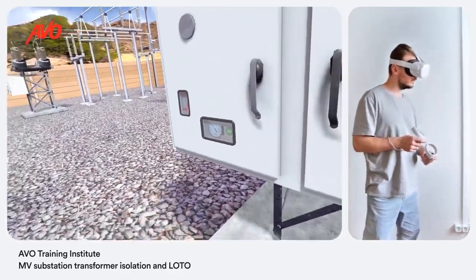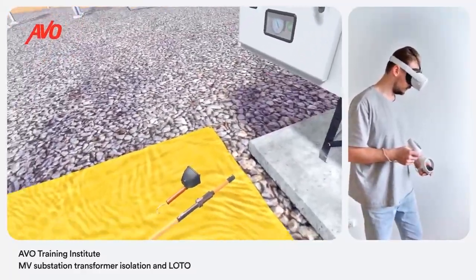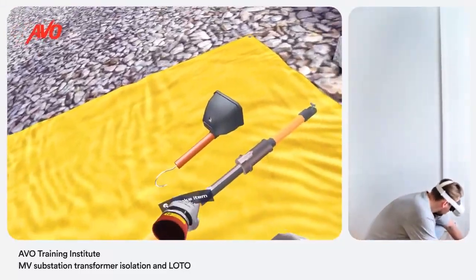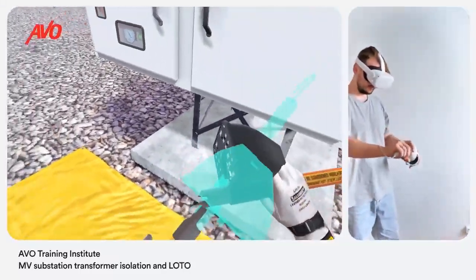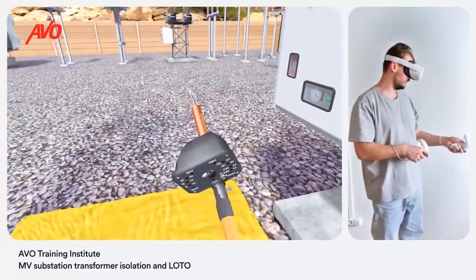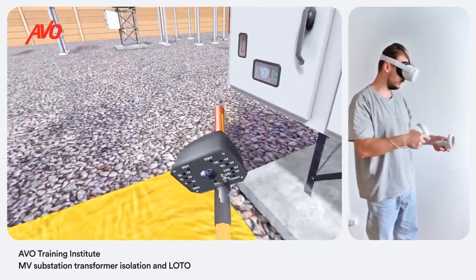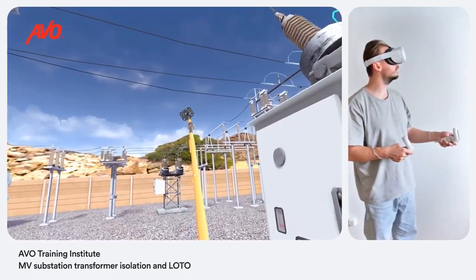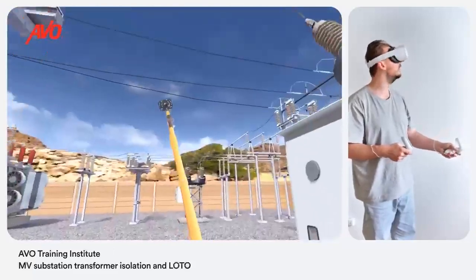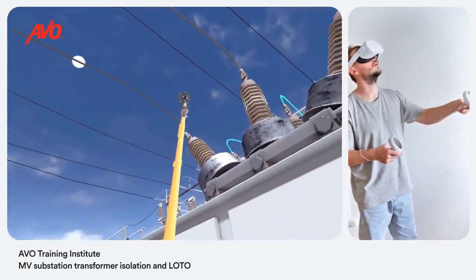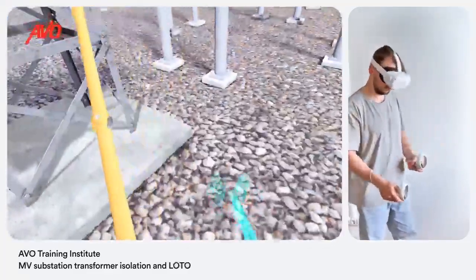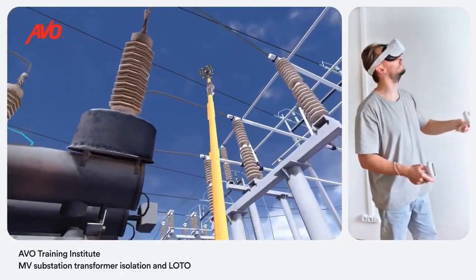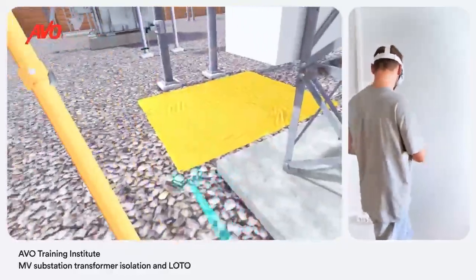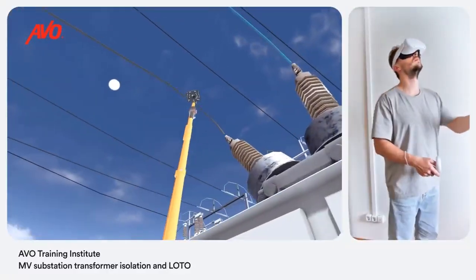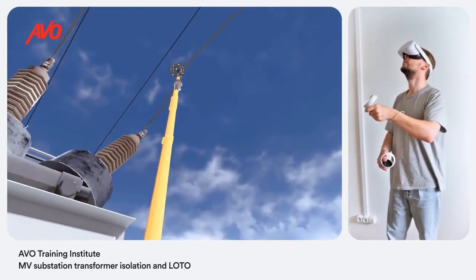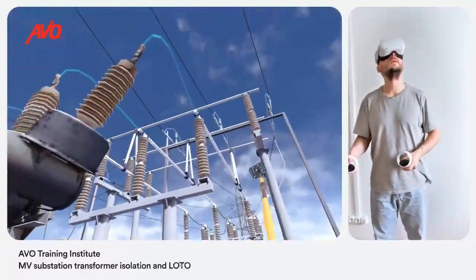Now, using a live line tester, verify zero potential on the load side of the feeding breaker. Grab a live line tester, attach it to a grip all stick, and turn it on. Test the meter first on a known source. Now test each phase at the load side of the feeding breaker. Retest the same known energized source to verify the tester is still working properly.